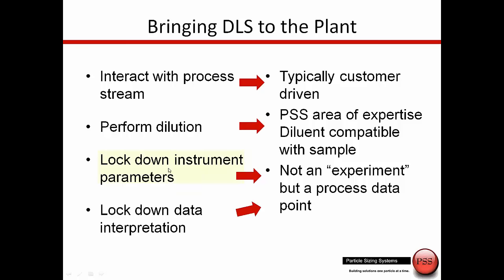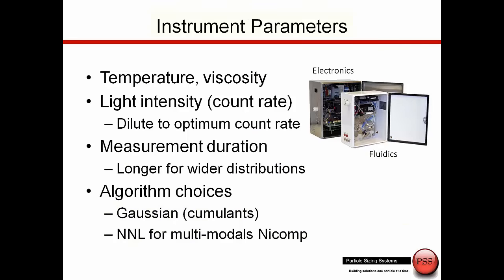When we're doing measurements in the plant, we kind of lock down all the instrument parameters, because this is no longer experimenting — this is turning into a process monitoring measurement. We lock down all of the parameters that could influence the result, and we also want to lock down the data interpretation, because typically we just want a single data point for process monitoring. The instrument parameters we want to control are temperature and viscosity. The light intensity, which is the count rate, we always want to optimize, because an optimum count rate gives us the best results with DLS. We don't use a neutral density filter with the online system, so we just control count rate by controlling dilution.